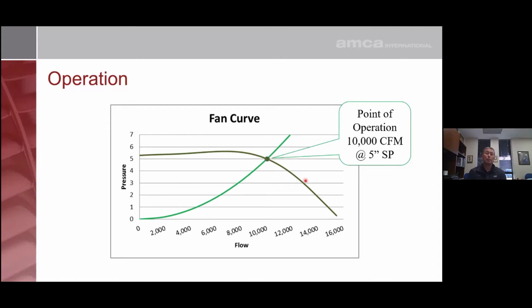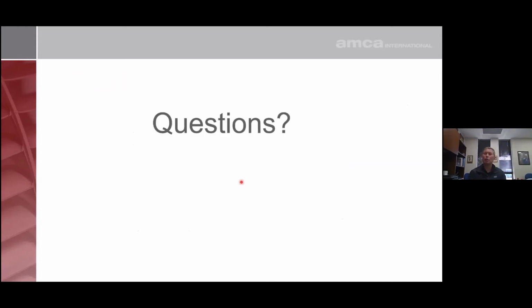Conversely, if you speed up the fan, it'll raise the whole fan curve up the system curve. If you decrease the fan speed, it'll just shrink the whole fan curve down the system curve. But that's basically how fans and systems interact. And that's also what determines where the fan's going to perform on the fan curve and where the system's going to perform on the system curve. Any questions regarding fan versus system curves, or how fans are tested?